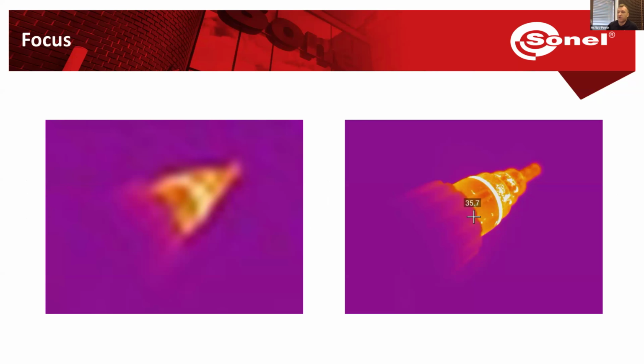What does this mean for us? First, on a blurry picture we cannot see what's actually there. Second, let's remember how the camera works: it measures the infrared radiation reaching the detector, which is then calculated into temperature using algorithms inside the camera. If the picture is blurry, the camera doesn't really know how much radiation it's getting, so the temperature readings will be untrue. That's why we need a sharp picture.